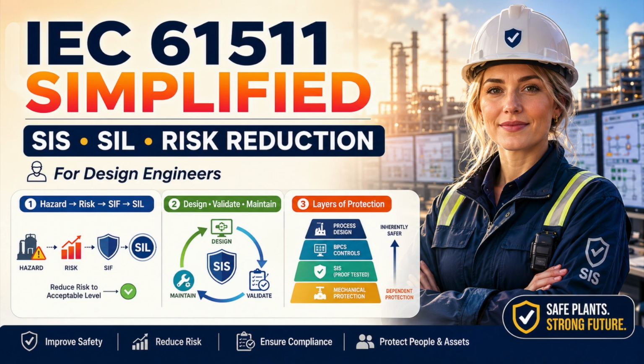For every safety instrumented function, you should be able to state exactly what hazardous event it addresses. You should know the initiating condition, the trip set point, the sensor arrangement, the voting logic, the required response time, the process safety time, the final elements, the safe state, the behavior on loss of power, the behavior on loss of instrument air, the fault response, the reset philosophy, the bypass rules, the proof test interval, the proof test coverage, the operating modes, the environmental conditions, the operator actions, the interfaces, the assumptions. If those requirements are vague, different disciplines will fill the gaps independently.